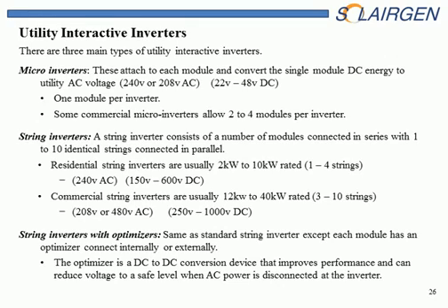Commercial string inverters, I think we have string inverters up to 50 kW now. It's a very large inverter, but it's mounted at the location of the PV array, which makes it inherently safer because we're not running DC conductors through conduits in other parts of the building, so you can safely go through the building and do what needs to be done and stay away from the PV array itself and be relatively safe. We do have a 1,000 volt consideration now for commercial PV systems. This is on the DC side. We're not looking at the AC side on that, but 1,000 volts DC is a greater arc potential, so we do need to be aware of that. String inverters with optimizers are starting to show up in commercial as well, but they don't dominate the commercial market.